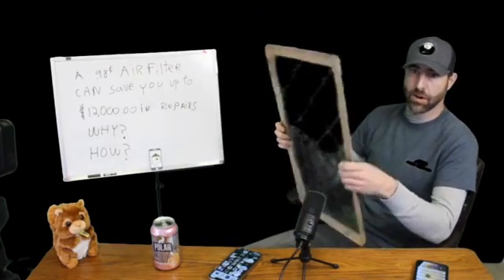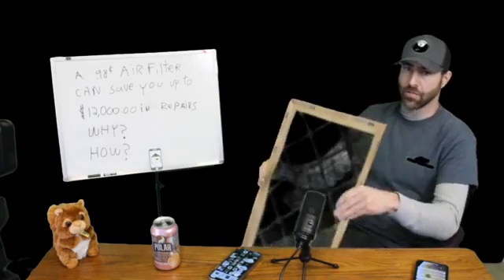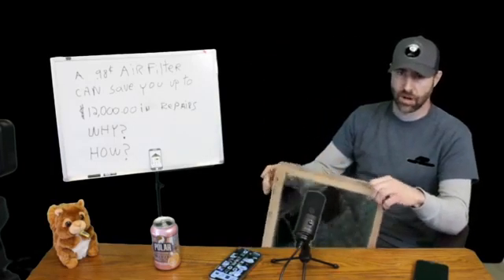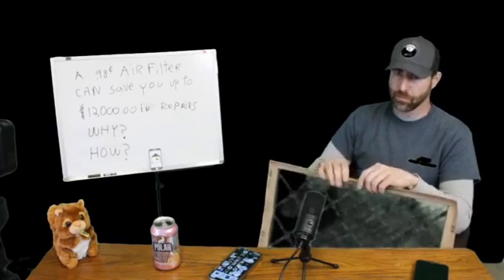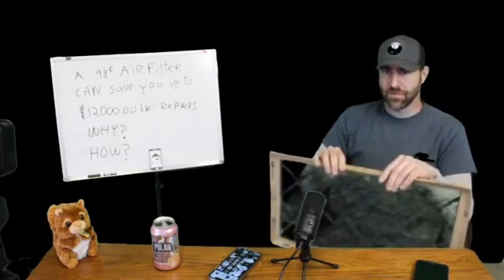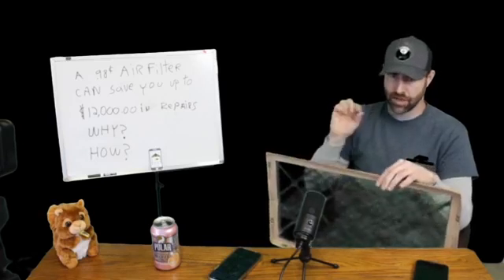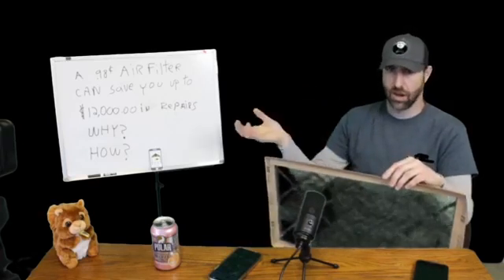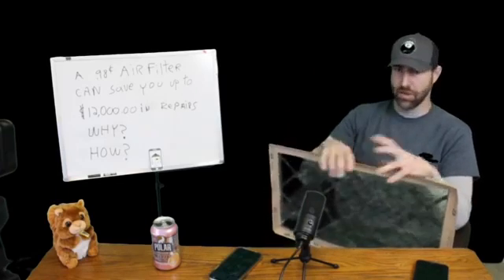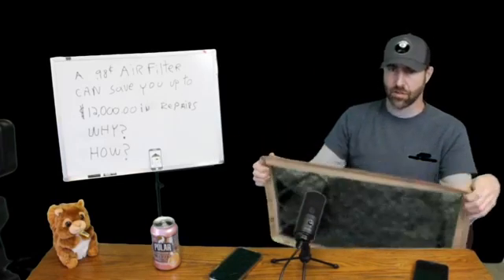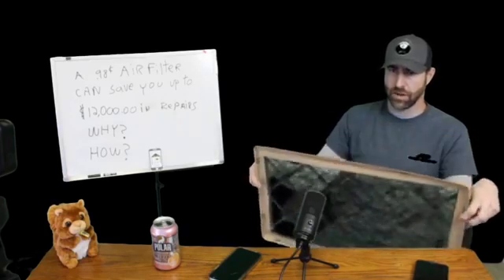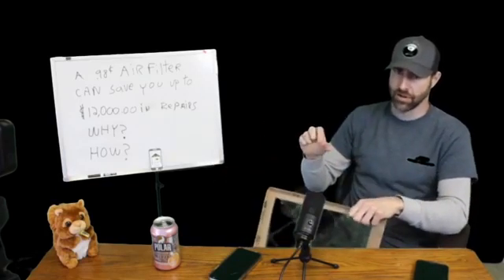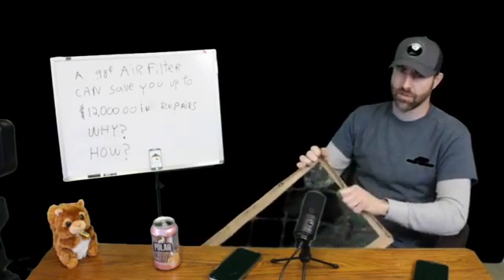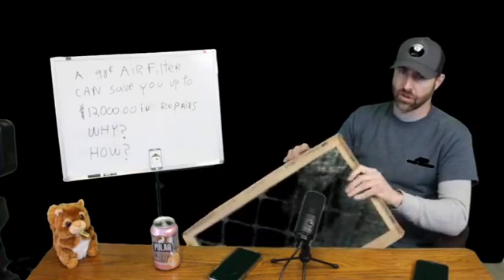So the cheaper ones start off like this. Then they have more expensive ones that are pleated, that are really heavy. You have to be careful. Some systems with ductwork design and system recommendations, you can't put the heavier ones in there. They can actually cause more problems for your system. You start going to restrict the airflow. See, the HVAC systems are designed very carefully. Everything has to be exact and precise, literally to every grill, every piece of ductwork, every piece of flex, every piece of pipe. Everything has to be designed custom according to your home. So just realize that when some manufacturers don't recommend having the pleated filters in there, those are the big heavy white ones, you can't put them in there. And if you're unsure, contact any HVAC contractor, he'll tell you.